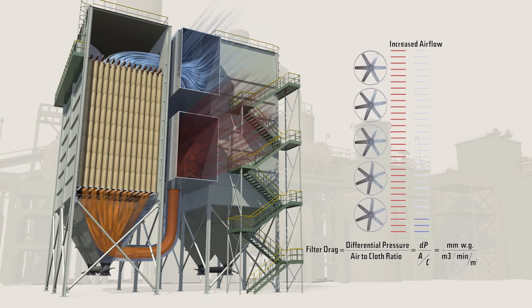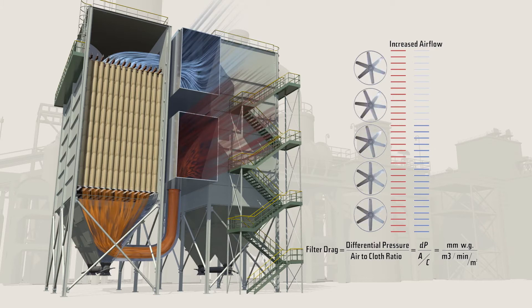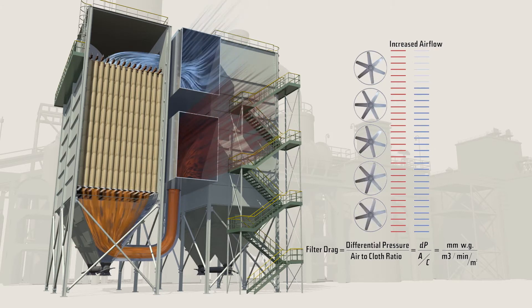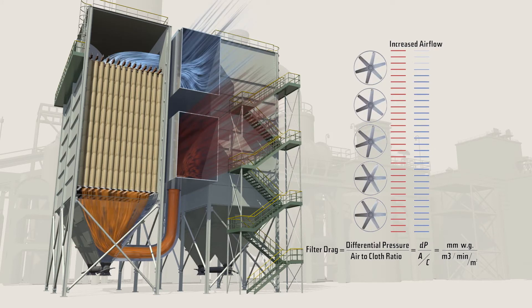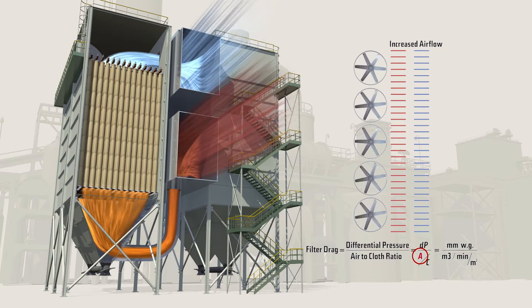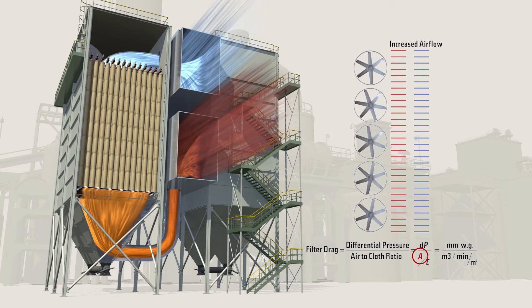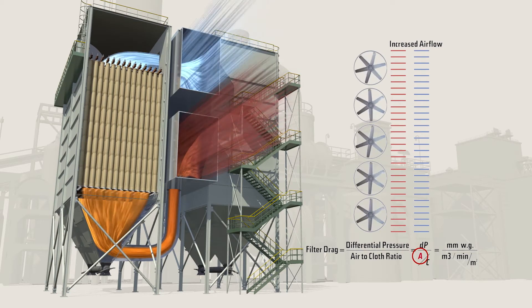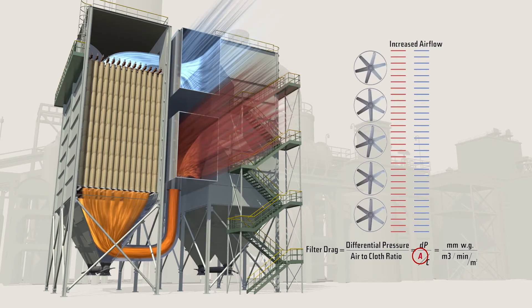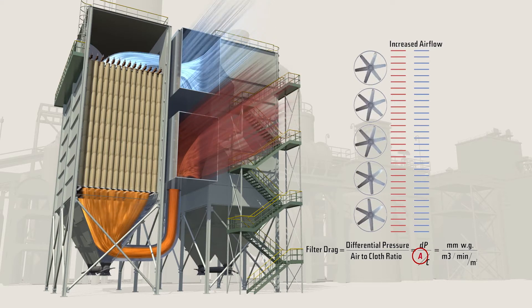If fan speed is fixed, by using Gore Low Drag filter bags, plants can operate at the same differential pressure and at a 10 to 15 percent higher airflow, allowing for more consistent boiler draft and potential increases in boiler energy output.